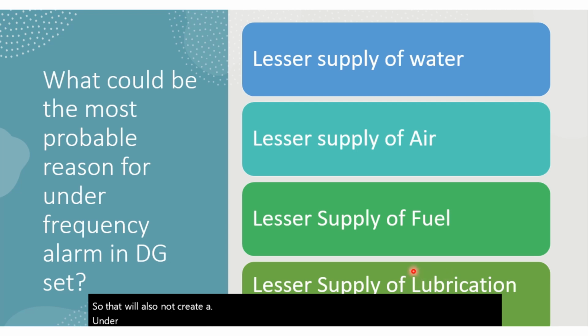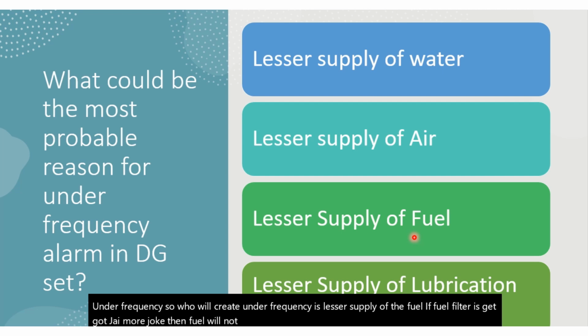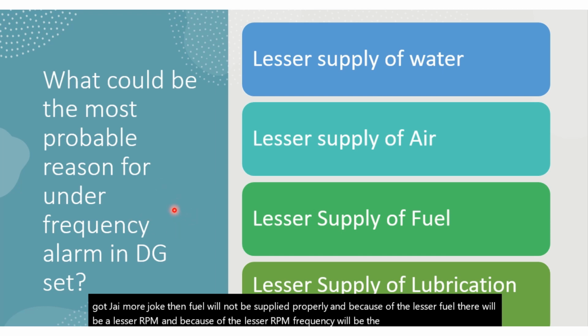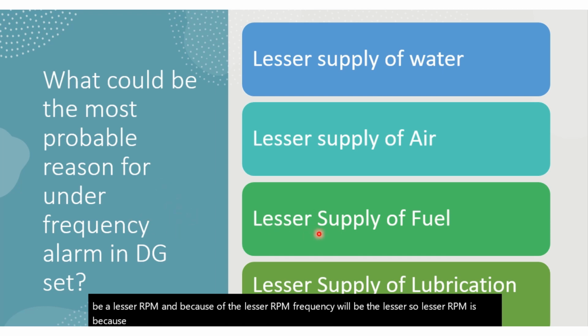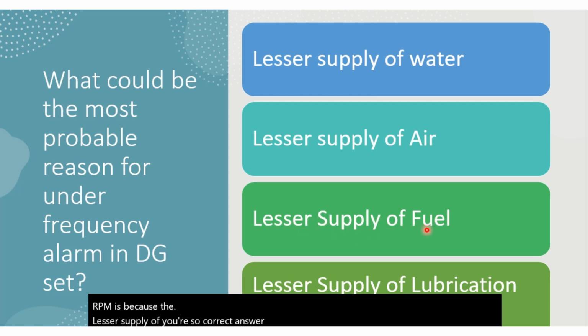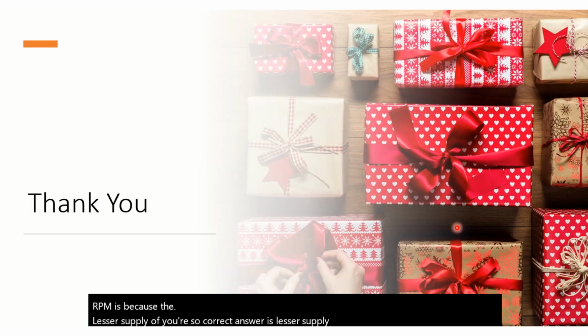What will create under frequency is the lesser supply of fuel. If the fuel filter is jammed or choked, then fuel will not be supplied properly, and because of the lesser fuel there will be lesser RPM, and because of the lesser RPM the frequency will be lower. So lesser RPM is because of the lesser supply of fuel. The correct answer is lesser supply of fuel.